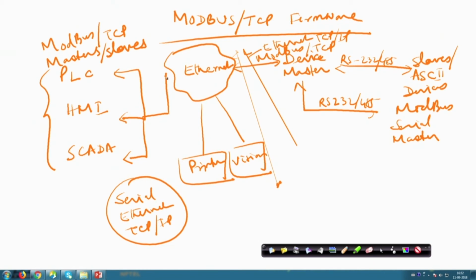As we can see over here, in this part we have all these PLCs, HMIs, SCADA, etc., communicating as either masters or slaves, typically masters, but they could be slaves as well. Here you could have all these different masters, and in this part all these different slave devices, with master-slave communication over different parts and different protocols. This part could use the Modbus TCP protocol, and this part the RS 232 485 between the device master and the slave. Like this you could extend it even further with other communication mechanisms in place, and this one could be Ethernet TCP IP, right. So, this is how it is going to work holistically.